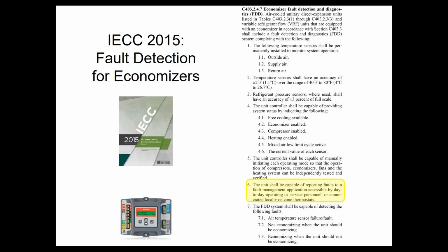Or if you don't have a BAS, it's a 2 rooftop project and there's nothing like that there, you can then choose to annunciate your alarms on the zone thermostat itself, and that would count as well. That takes a very specialized thermostat, but not a very expensive thermostat. There were 3 thermostats that used to be able to do that. Now I think we're up to like 8 or 9 models.